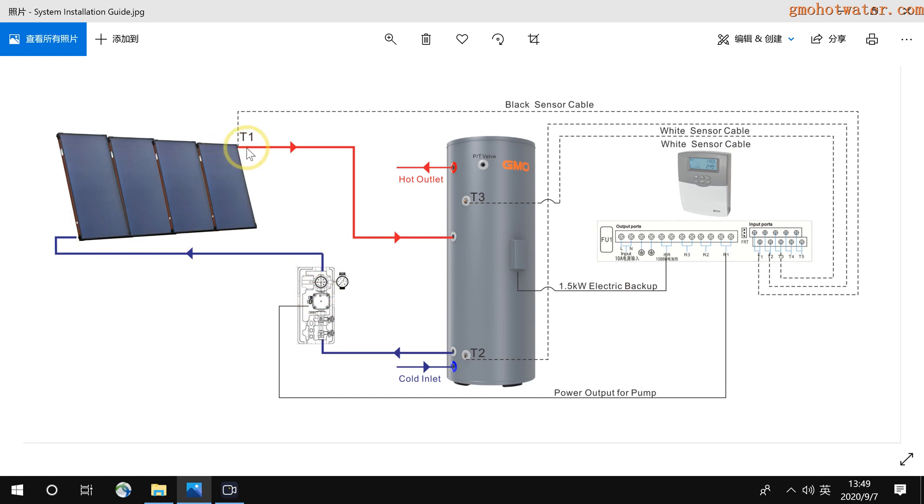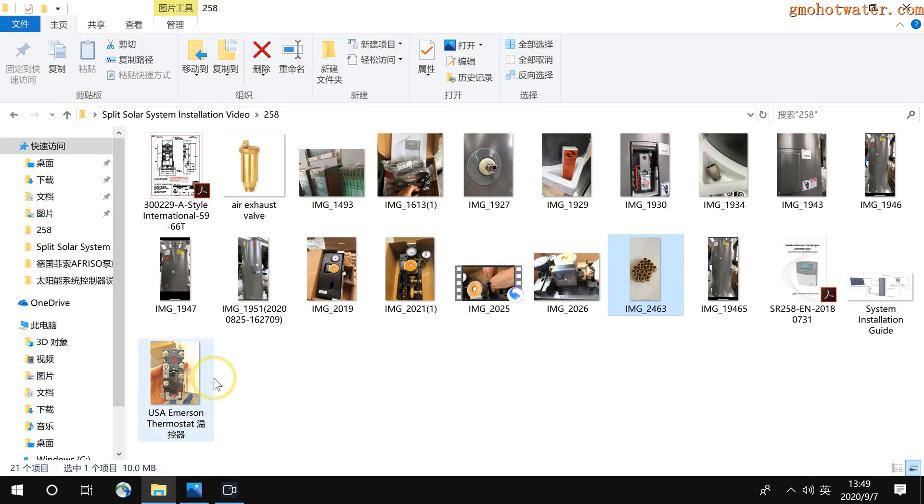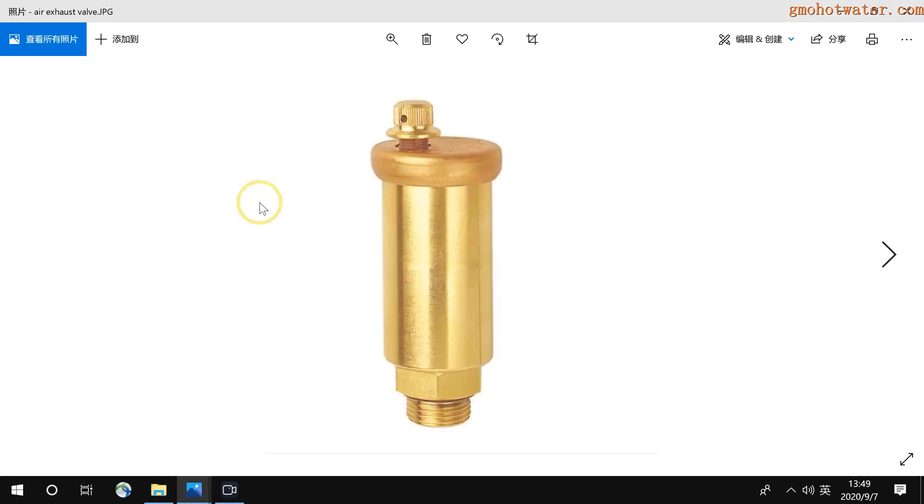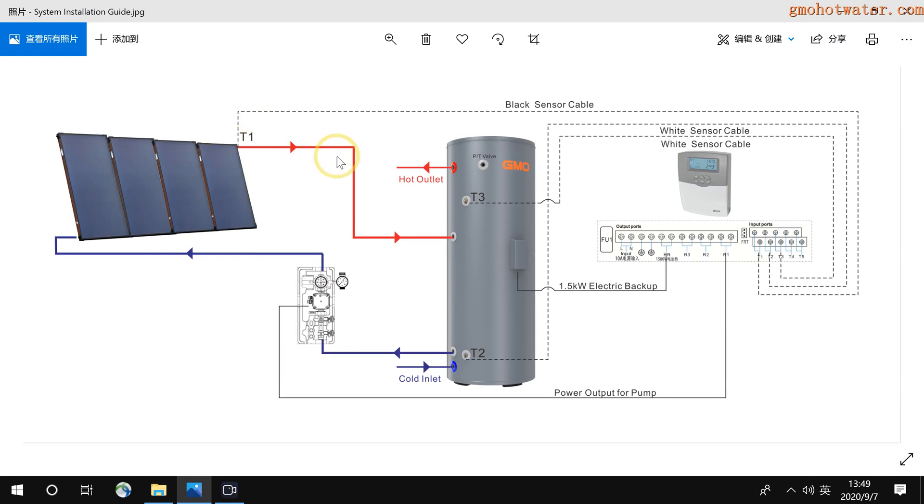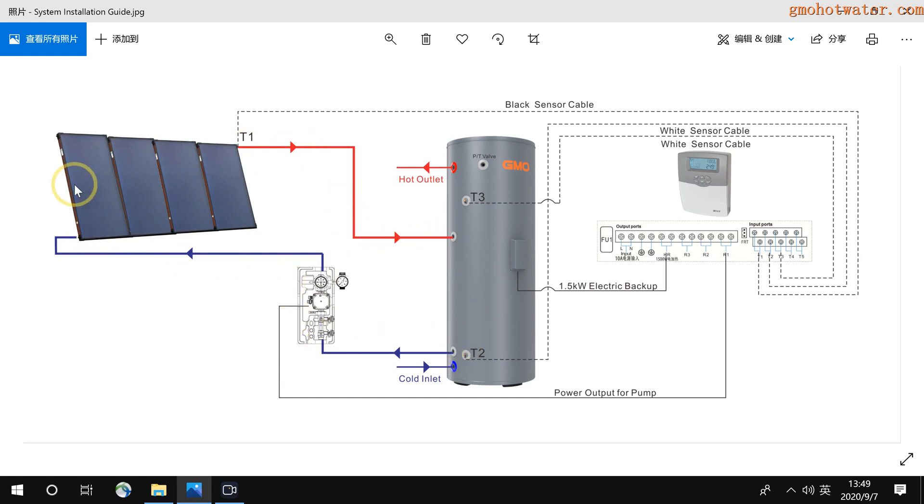My advice is, at the hot outlet, you can equip it with an air exhaust valve, like this picture. You can find it in your market. The function is, maybe there will be some little amount of air on the top of the system. Then it will have influence on the circulation. If you have an air exhaust valve here, it will increase the circulation efficiency.